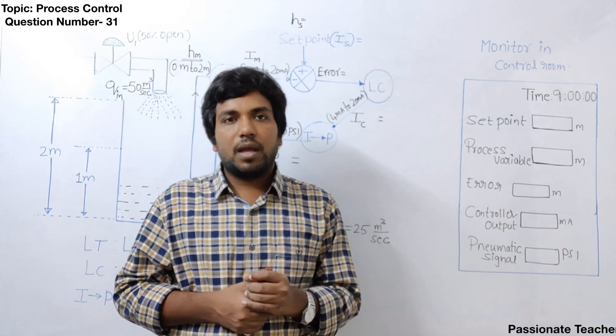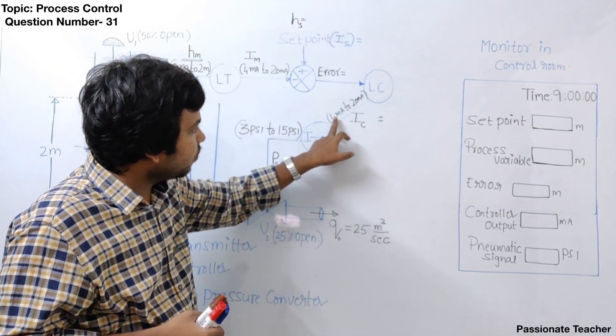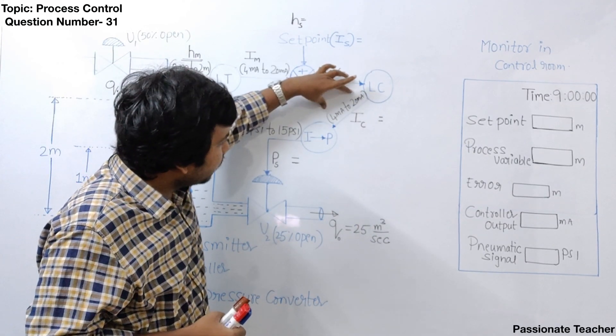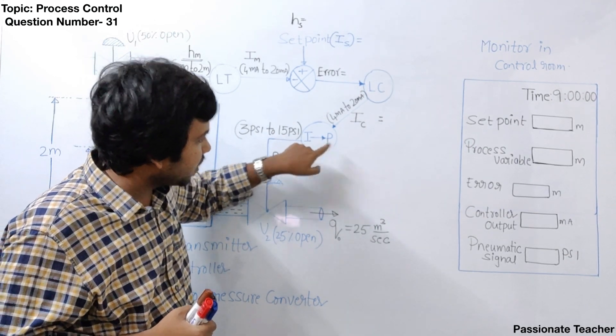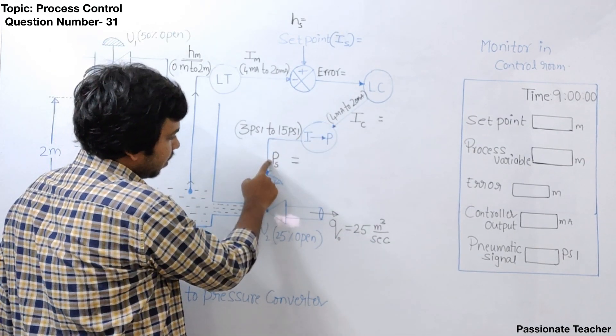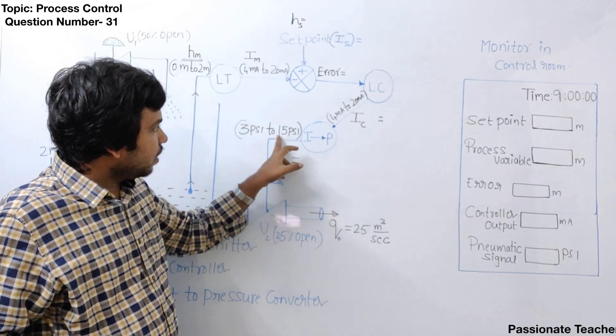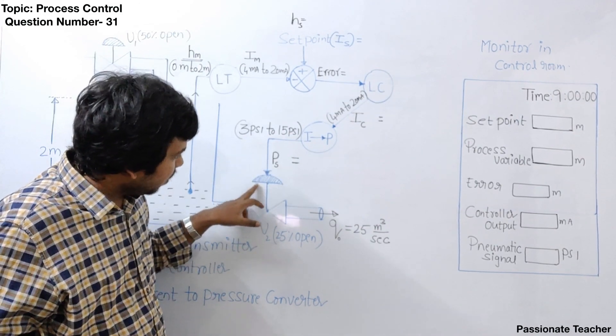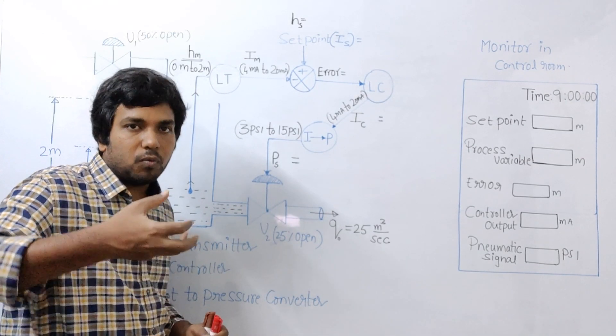The level controller is designed with electronic components and generates current in the standard range of 4 milliampere to 20 milliampere. Whatever current is generated by the controller is given to the I2P converter — that is, a current-to-pressure converter — because this current has to be converted to pressure before being applied to the pneumatic control valve. Whatever pressure is generated from the I2P converter is then given to the pneumatic control valve.